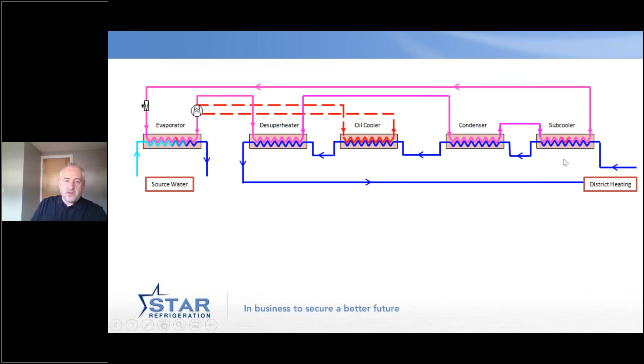In terms of the efficiency, just to go back over, we see about a 1.5% efficiency change in terms of the forward temperature. So if we're flowing at 80, that's 1.5% worse than 79. And the delta on the network, if instead of being 20 Kelvin, we're 21 Kelvin, we'll be 0.5% better. And on the cold end of the system, if instead of being at 5 degrees, we're managing to use 6 degrees, we'll be about 1.5% better. So 1.5, 0.5, and 1.5 is the way that we're impacting the system by managing district heating better.